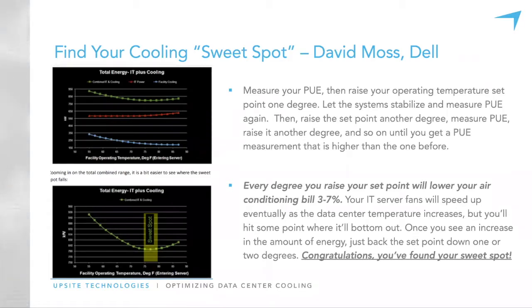You continue this process - and I'm sorry, I left out an important point: after every degree, you want to measure your PUE again, to see where you're at and whether that ratio is changing. You continue until you get a PUE measurement that's higher than where you started. Once you see that, you back it down a degree or two, and that's where David Moss says you'll find your sweet spot.